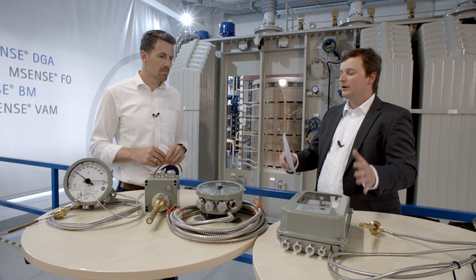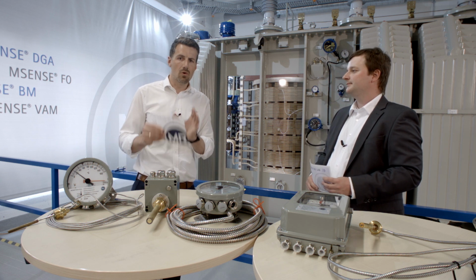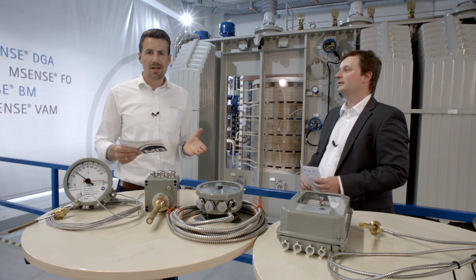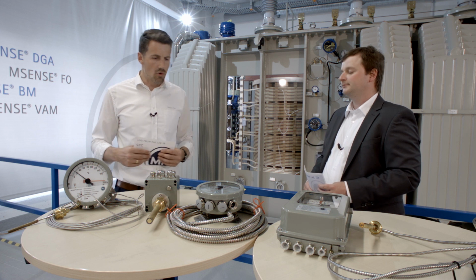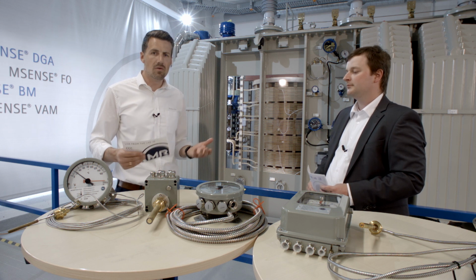Whereas, for example, the Compact is a compact device in itself, which means the transmission, for example, the 4 to 20 milliamp analog output, is included in the device itself and not somewhere else. This is why it is called Compact, for example. But all in all, for all applications at power transformers, we can recommend our entire thermometer lineup. Okay, so both versions are available for all kinds of applications, for all kinds of transformers. At the end of the day, it's a philosophy question. All types are looking very robust, very massive, premium quality, manufactured by MESSKO MR here in Oberursel.